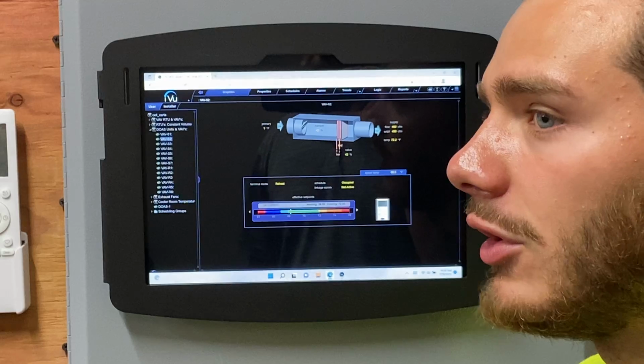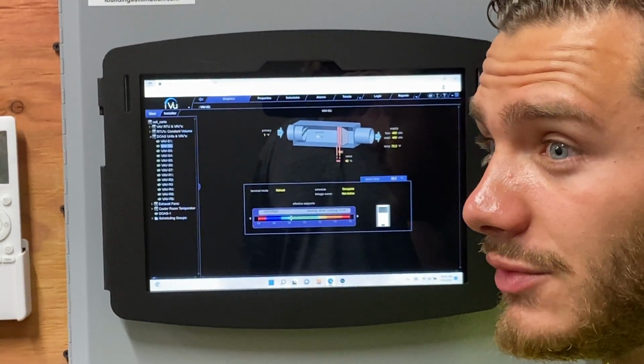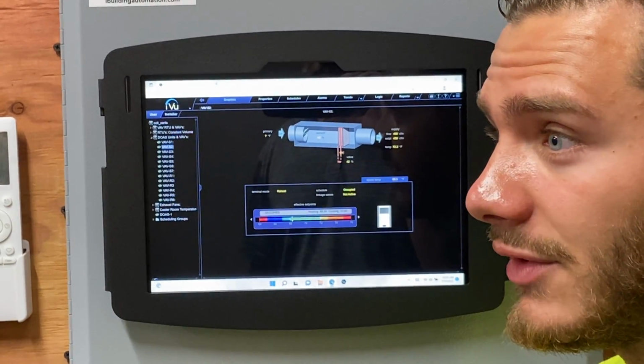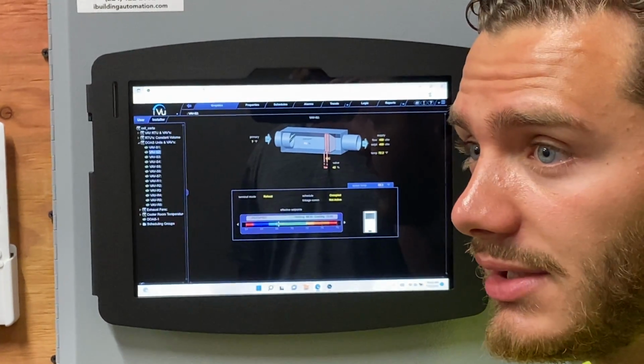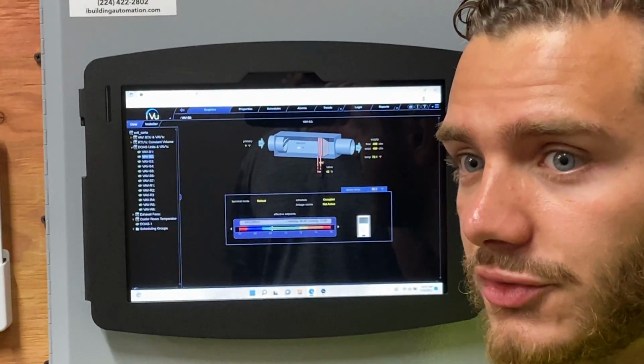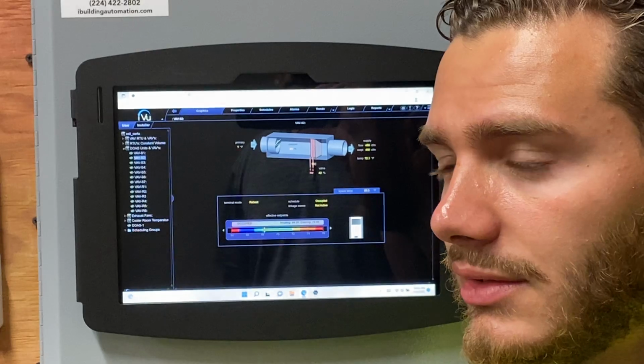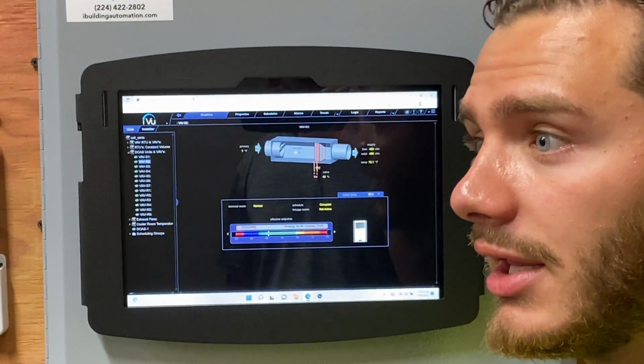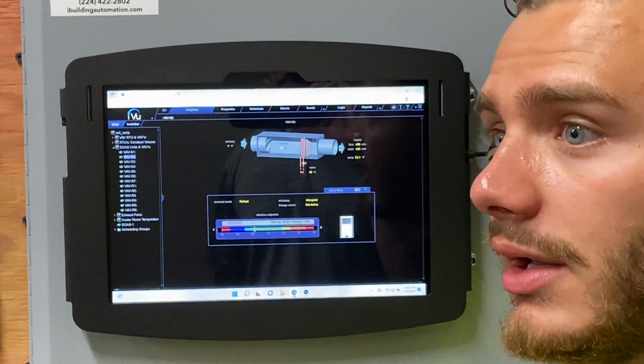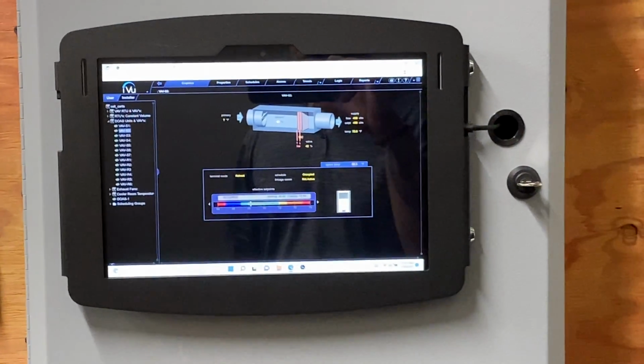So for the lab space, we'd go 72 and then 4 degrees up to 76 for the office, and you'd be able to go down to 70 and 74. Those are your middle points. So if you set the office at 72, plus or minus 2, that's the coldest it's going to get. Okay, I'm going to take notes on that.